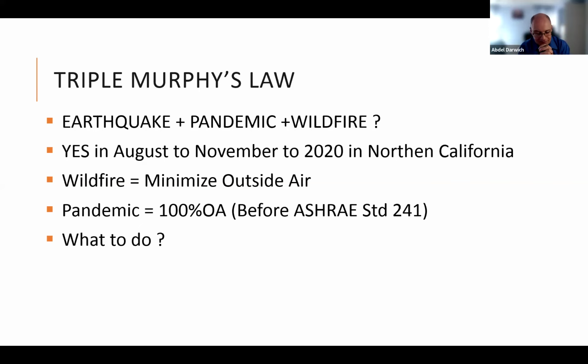So I was getting phone calls asking, what do I do? Pandemic says go to 100% outside air, but wildfire tells me to minimize outside air. And even if I find a filter, if we go to 100% outside air, can I find one that will withstand the earthquake? Because we have a requirement that any equipment chosen in a hospital needs to be operationally excellent — and there was none.